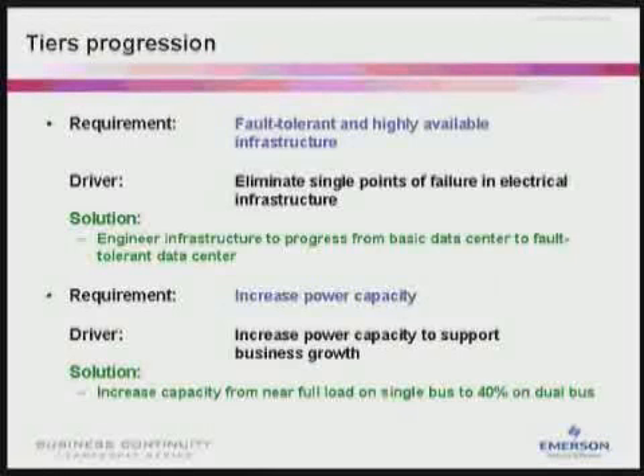The project was broken down into business requirements and drivers and solutions. The first requirement was to create a fault-tolerant and high availability infrastructure through the elimination of single points of failure. The solution was to engineer infrastructure to progress from a basic data center to a fault-tolerant one. Increased power capacity was needed to support business growth. A solution was to increase capacity from near full load on a single bus UPS to 40% on a dual bus system.